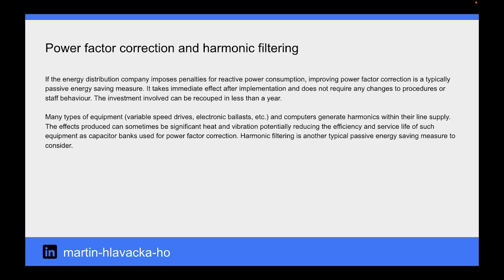If the energy distribution company imposes penalties for reactive power consumption, improving power factor correction is a typically passive energy saving measure. It takes immediate effect after implementation and does not require any changes to procedures or staff behavior. The investment involved can be recouped in less than a year.